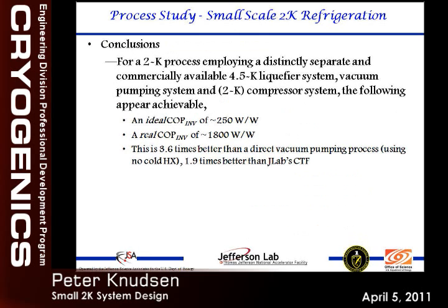So, summary, as I mentioned, 1,800 watts per watt for the real COP looks like it's achievable. That corresponds to an ideal COP of 250 watts per watt. This is about 3.5 times better than direct vacuum pumping, and about 2 times better than JLab CTF.